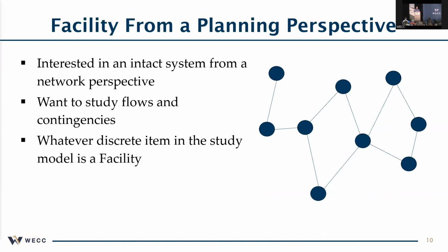They can take one of those lines out or two lines out and look at the contingency, see how that shifts flows. So they're looking at it static and then remove something, try to break, see what's going to change flows, and do those flows meet those facility limits that have been published. So it's very important for them to know what the real limits are, because when they do these contingencies, they won't really know, do we have a problem here, or was there slop built into this? Or do we have the right numbers? And if you don't have the right numbers and don't have the right facility limits, then all your predictions for your contingencies and events are not going to be accurate. So from planning perspective, that's what they want to know.